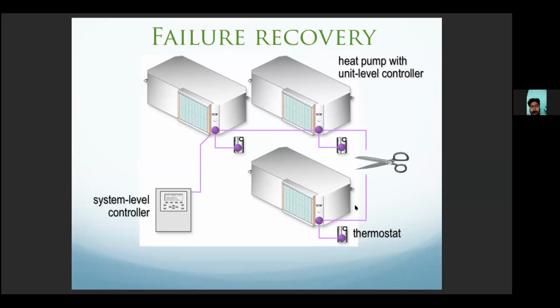So now in this scenario, we have a heat pump with a thermostat, and it looks like there was some construction and the cord was cut. Now in this scenario, what this heat pump is going to do is that the unit level controller is programmed in a way that it is told if you do not have any input from the system level controller, or if you are by yourself, then operate at X, Y, Z parameters. So it is going to start doing that as soon as it loses connection to the system controller.